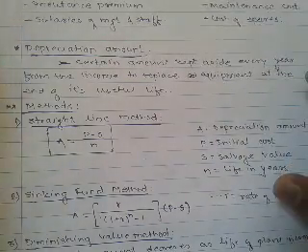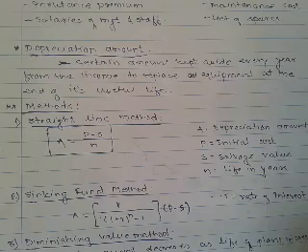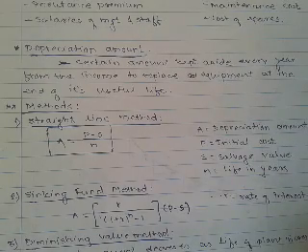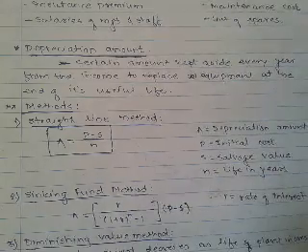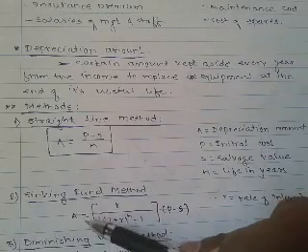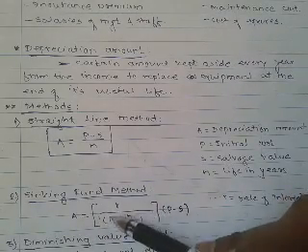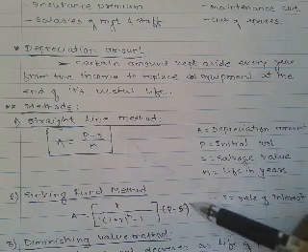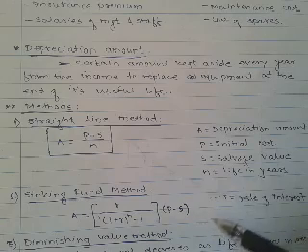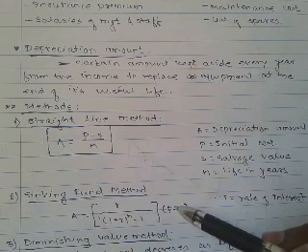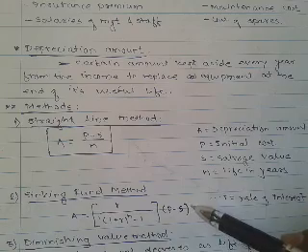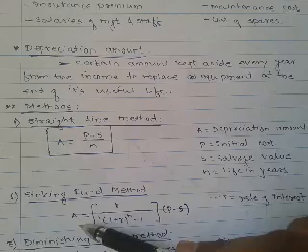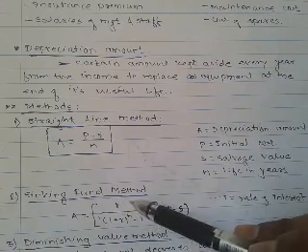Second method is sinking fund method. In this sinking fund method, the amount kept aside increases with increasing the life. So amount kept aside increases with increasing the number of years. So this can be calculated by using this formula: A is equal to [r upon ((1 plus r) raised to n minus 1)] into (P minus S), where P is initial cost or initial investment, S is salvage value, A is depreciation amount or depreciation cost, and r is nothing but rate of interest.